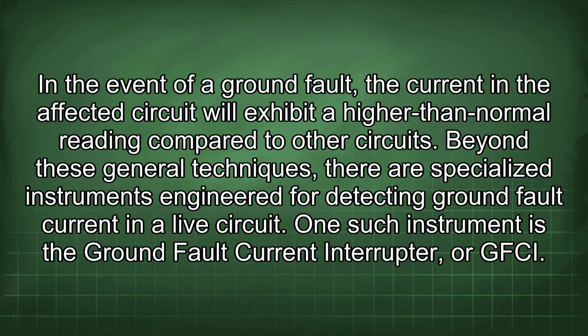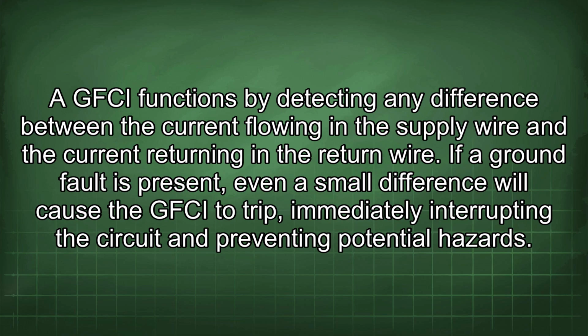Beyond these general techniques, there are specialized instruments engineered for detecting ground fault current in a live circuit. One such instrument is the ground fault current interrupter, or GFCI. A GFCI functions by detecting any difference between the current flowing in the supply wire and the current returning in the return wire. If a ground fault is present, even a small difference will cause the GFCI to trip, immediately interrupting the circuit and preventing potential hazards.